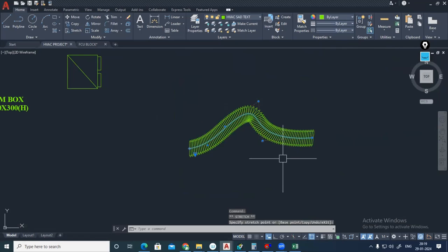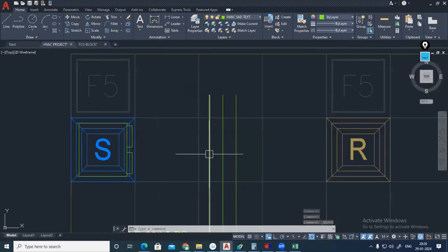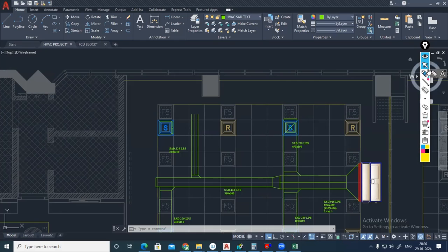Now I have to connect this one here. Before that, I should connect the collar in the duct itself. See, if you have only one flexible duct there, then in the flexible duct you can provide an RVCD that will adjust the flow rate. Or instead of that, here in the branch, if you provide an RVCD, this one also will adjust. Even if there are two flexible ducts, since it is connecting to a single plenum.